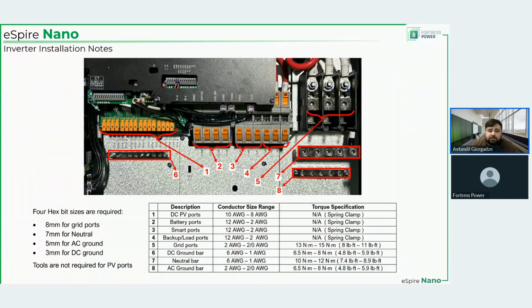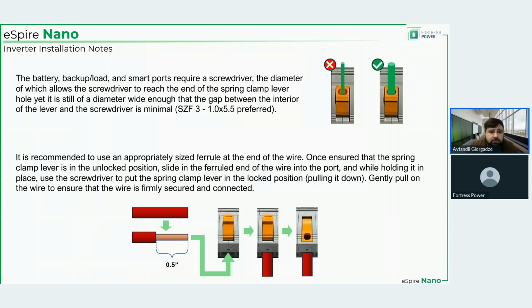Now, next, I told you that I would show you what precautions to follow when putting in these, or when trying to operate these spring load mechanisms. So first and foremost, you want the screwdriver or the rod that you put into that hole to be long enough to reach the end, and also not have a gap between the walls. I personally, unfortunately, did not use a proper screwdriver, and when I was closing this orange thing in which you stick the screwdriver, it broke on the bottom. Happily, that was in the lab. I did not damage a customer's system, but please pay attention to that. Otherwise, damage cannot be ruled out.